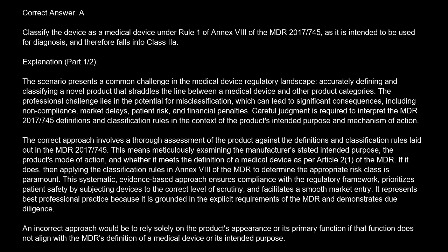The correct approach involves a thorough assessment of the product against the definitions and classification rules laid out in the MDR 2017/745. This means meticulously examining the manufacturer's stated intended purpose, the product's mode of action, and whether it meets the definition of a medical device as per Article 2(1) of the MDR.